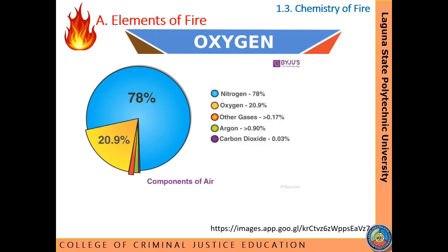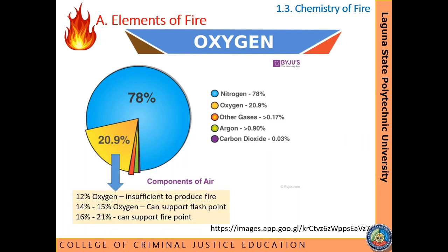The third element of fire is oxygen. Oxygen in air is the common oxidizing agent that combines with fuel vapor. The components of air are: nitrogen at 78%, oxygen at 20.9% (sometimes rounded to 21%), and approximately 1% inert gases such as argon and carbon dioxide. Note that 12% oxygen is insufficient to produce fire; at 14–15% oxygen it can support flash point; and at 16–21% it can support fire point.